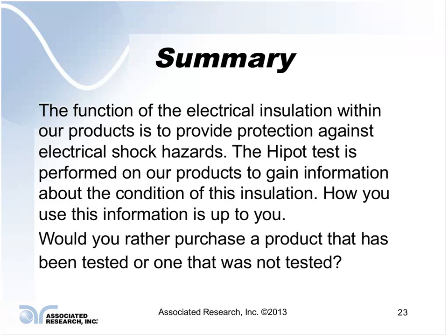It says, some years ago I conducted several tests on a group of power supplies in parallel that we performed a Hipot test on. I ran the tester for 8 hours a day, 5 days a week. Finally, after about 1.5 weeks, I detected some insulation abnormalities.